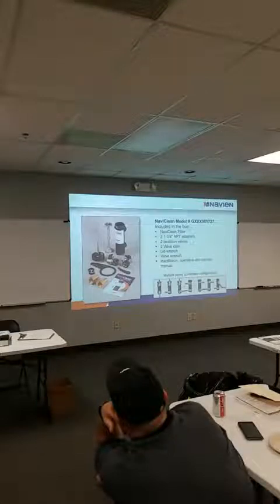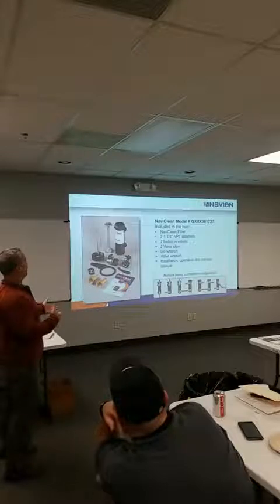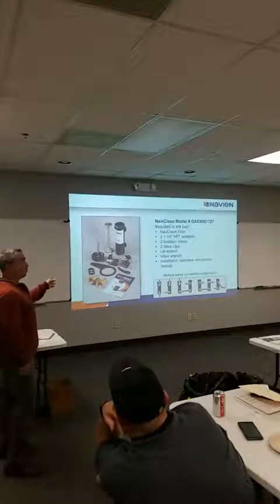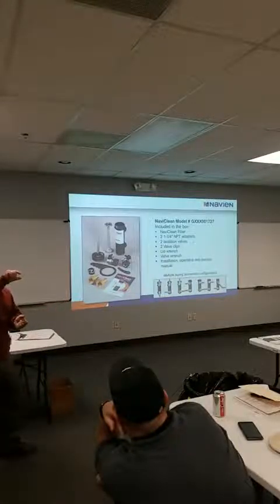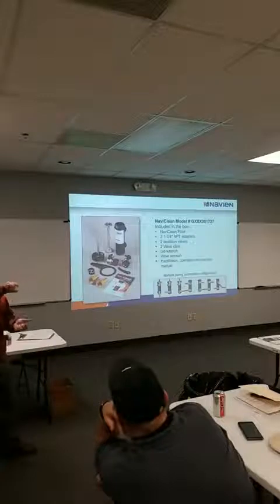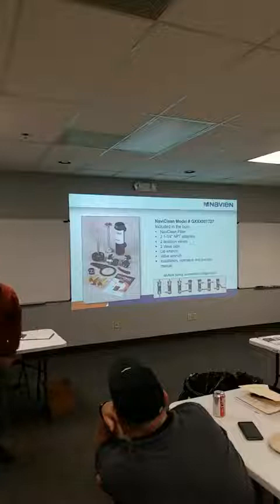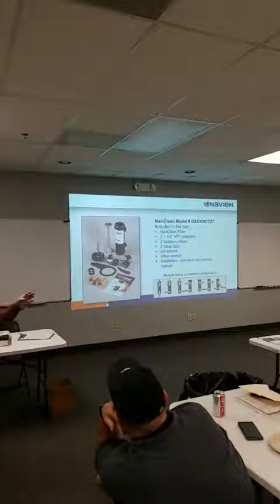What's the physical size of that? This thing's about this big. I sell commercial ones that are, this big off the floor. So, just depends on your system and the piping. We use these little ones on bigger systems and just tee it off the return pipe. So, we might not catch everything on the first run, but over time. So it's a parallel loop, so you can valve it, clean it without even touching the system. Exactly, you don't have to turn anything off. Just isolate it, dump it, away you go.